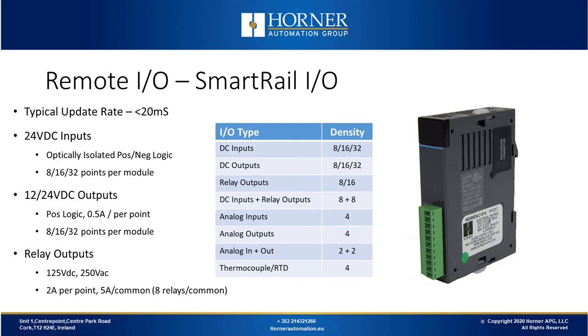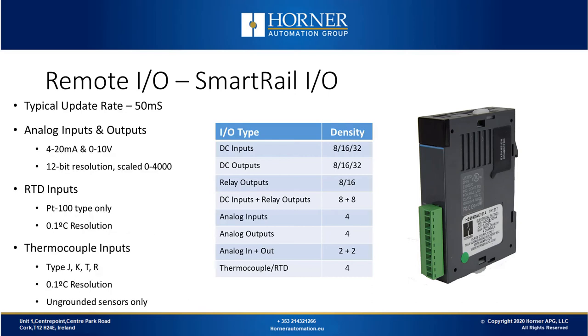We support 12 or 24 volt inputs as well as 12 or 24 volt outputs, which are isolated on the input side. These are typically available with half amp drive capability. For digital inputs and outputs, you can have 8, 16, or 32 points of density. Relays are really popular for Smart Rail, supporting high voltage DC and high voltage AC — 2 amps per point and 5 amps per common. For a 16-point module, there are 2 commons, so there's higher capability in terms of current. On the analog side, the update rate is typically around 50 milliseconds. It supports 4 to 20 milliamps and 0 to 10 volts, with 12-bit resolution scaled at 0 to 4,000. On the RTD side, it only supports PT100 sensors. It supports the most popular thermocouple types J, K, T, and R, but only ungrounded sensors can be used with Smart Rail for thermocouple.